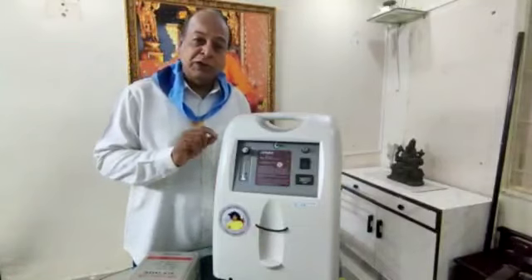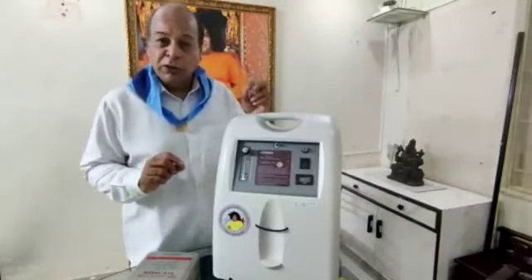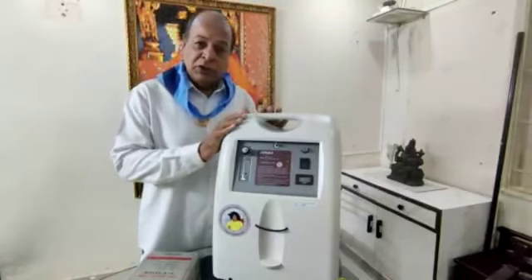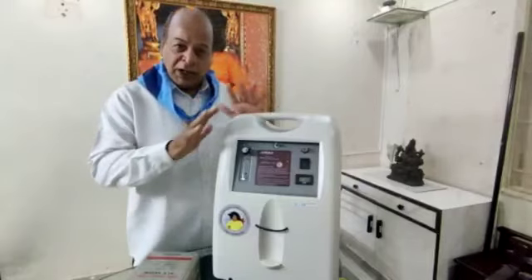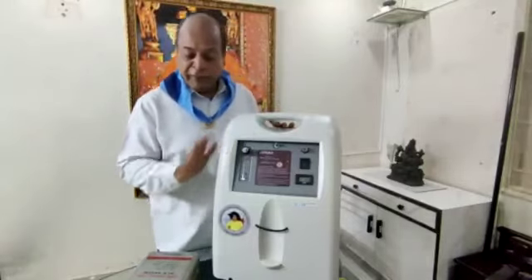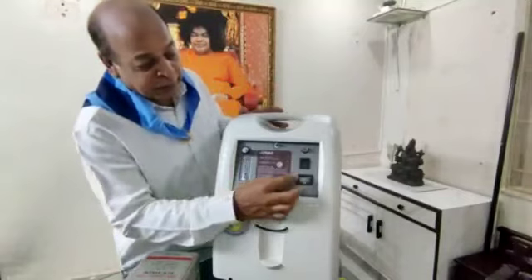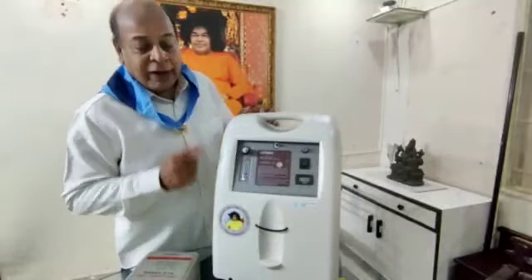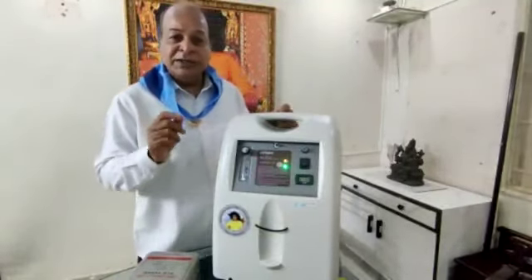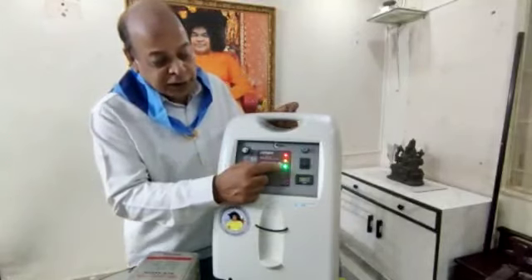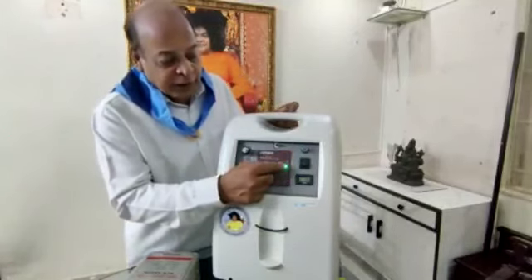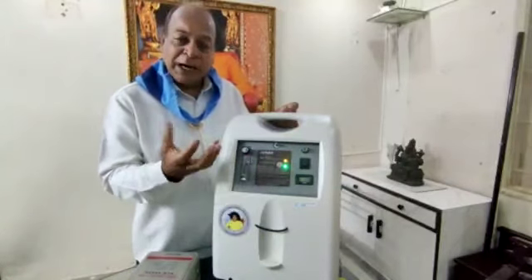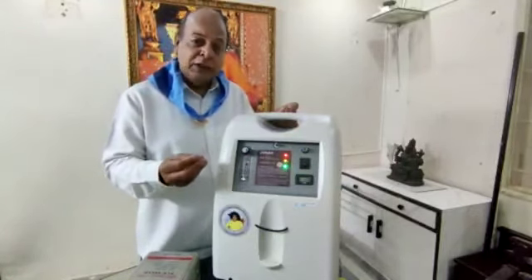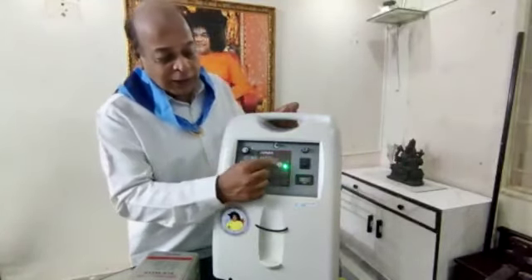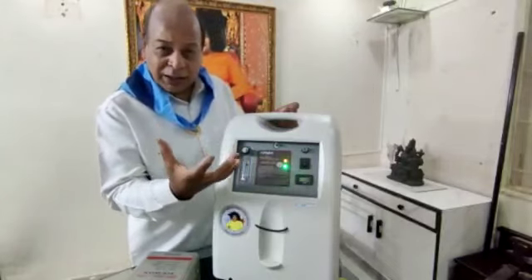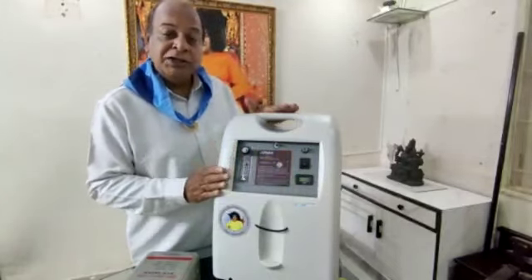Don't plug the oxygen concentrator directly into 220 volts. If you do so, the oxygen concentrator will fuse out. It will not work at all. Now we have connected it, and once we do it, we power it on. Every concentrator takes about 15 to 20 seconds to power up. Initially, the green, yellow and red lights will start blinking. After 10 to 15 seconds it stabilizes, the green light becomes darker in shade, and the machine is ready to use.